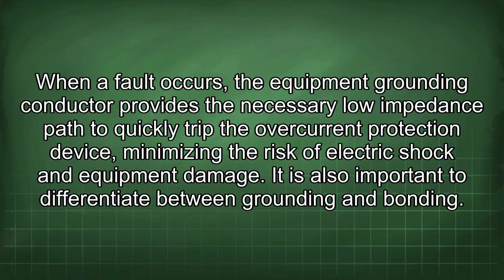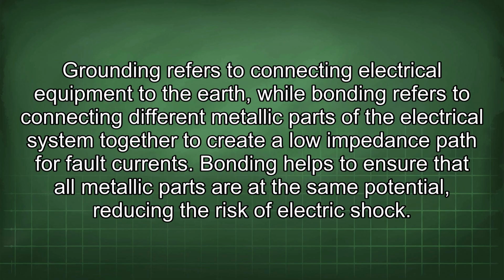It is also important to differentiate between grounding and bonding. Grounding refers to connecting electrical equipment to the earth, while bonding refers to connecting different metallic parts of the electrical system together to create a low impedance path for fault currents. Bonding helps to ensure that all metallic parts are at the same potential, reducing the risk of electric shock.